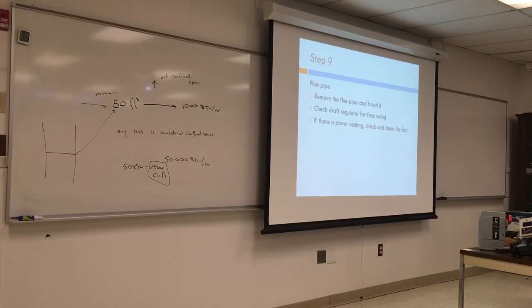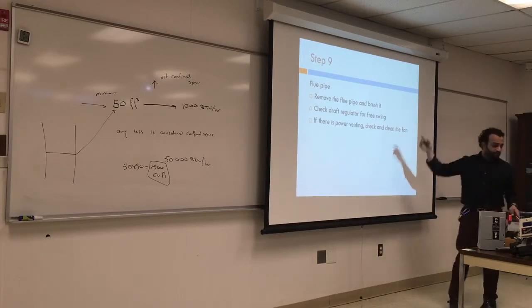Step 9, the flue pipe. What's a flue pipe? That's where the flue gases come out. Remove the flue pipe and brush it. You'll see a lot of accumulation in there. Check the draft regulator for free swing. What is the free swing?